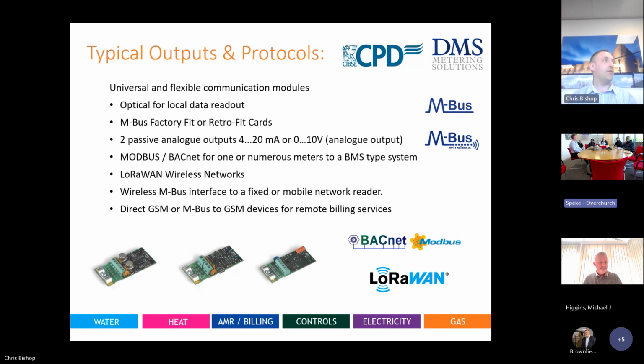So that's just a 2-core cable, like a daisy chain, star topology, bus network. Analog outputs: now a lot of people are taking flow rate data from heat meters instead of adding another flow meter into the system itself. So it's using a heat meter to cover both aspects, both heating and control. Flow rate output 4-20 milliamp, 0 to 10 volts, kind of like inverter control. Modbus and BACnet are still really the default because most data collection requirements go into a BMS. We all know why that happens.